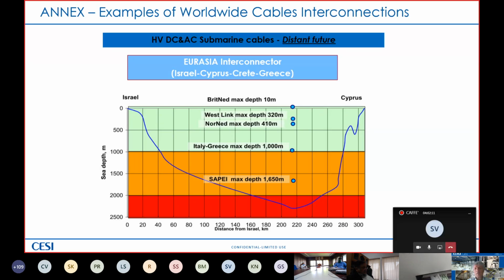Again, in other sectors of the northern seas, we have the West Link or the NorNed, where the maximum depth is between 300 and 400 meters. So installing windmills is a little bit more complicated if they are not floating. But for sure, cable can still be installed.